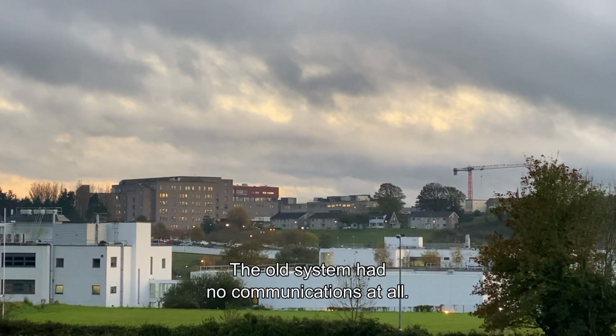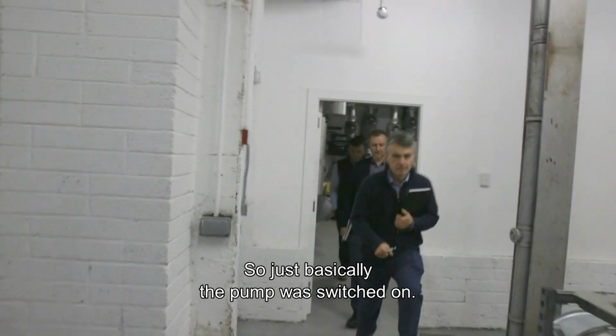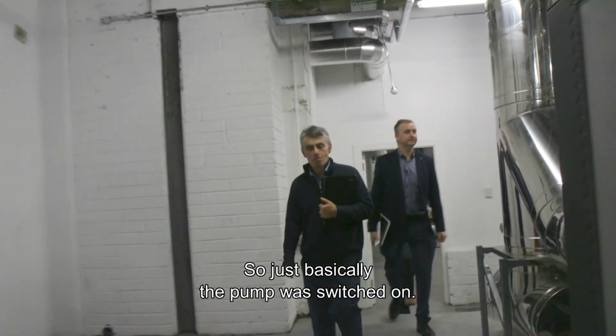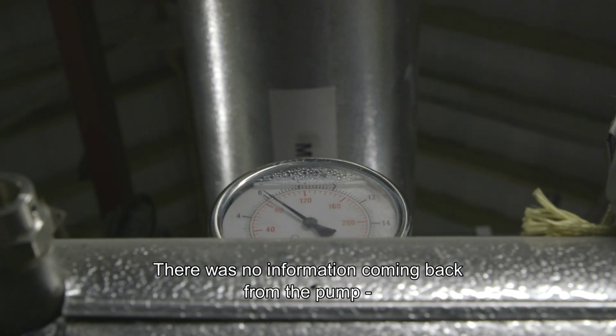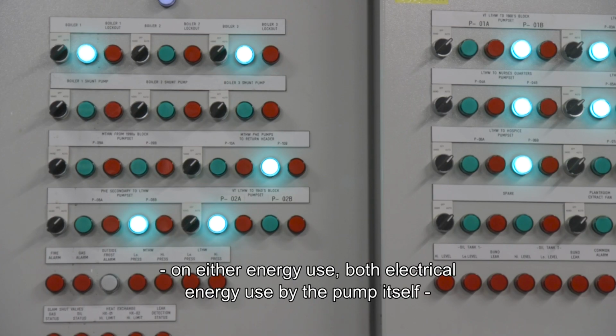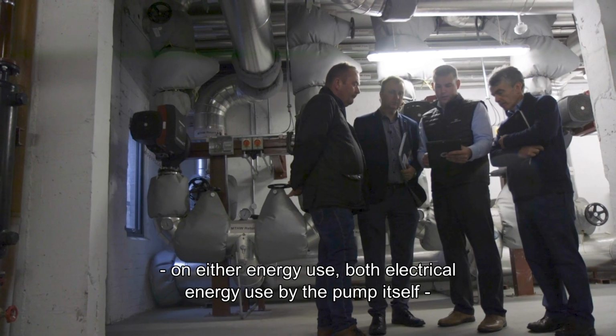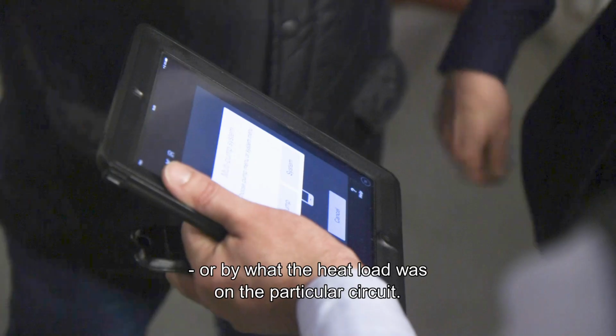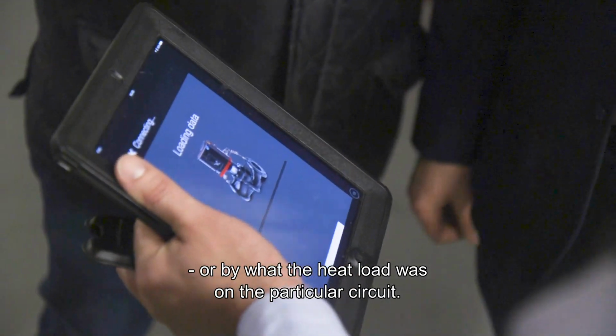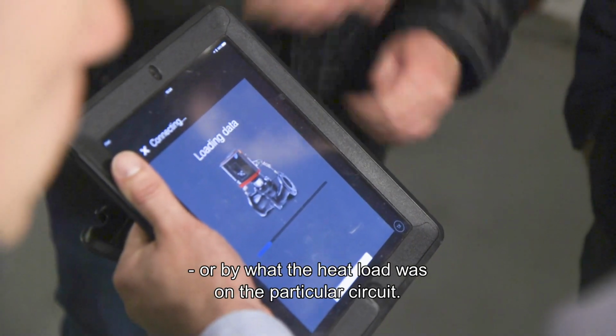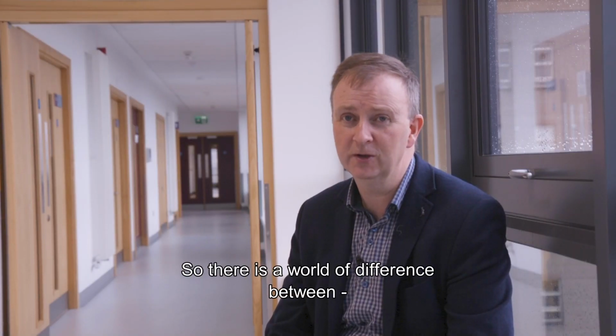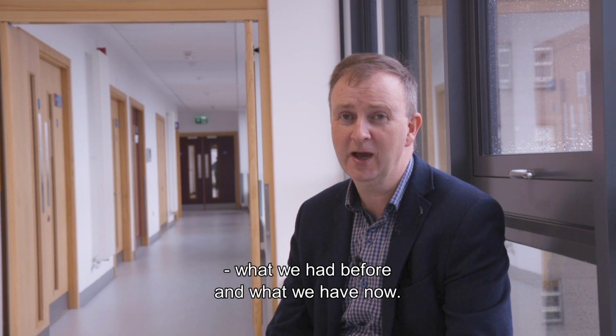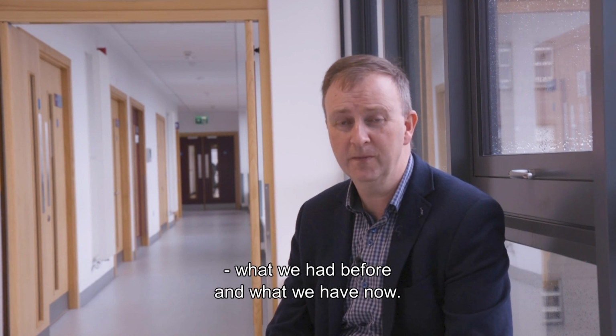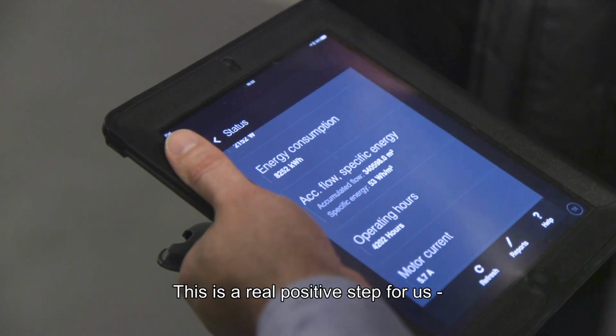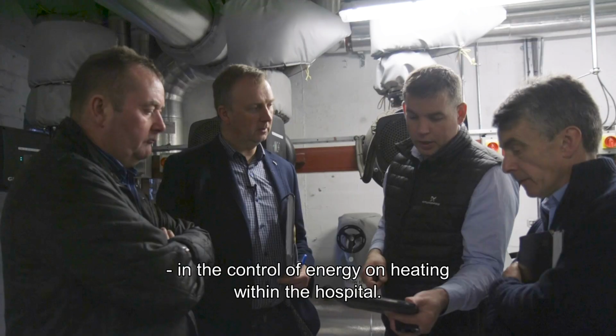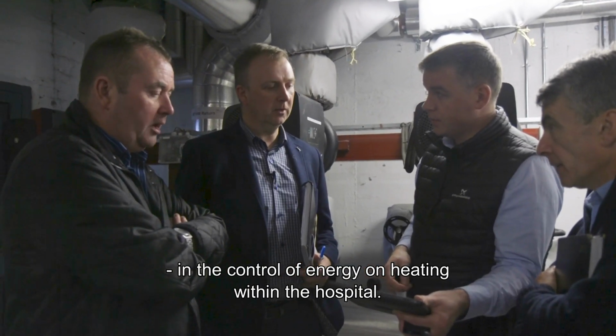The old system had no communications at all, so basically the pump was just switched on. There was no information coming back from the pump on either energy use, both electrical energy use by the pump itself or by what the heat load was on the particular circuit. So there's a world of difference between what we had before and what we have now, and this is a real positive step for us in the control of energy on heating within the hospital.